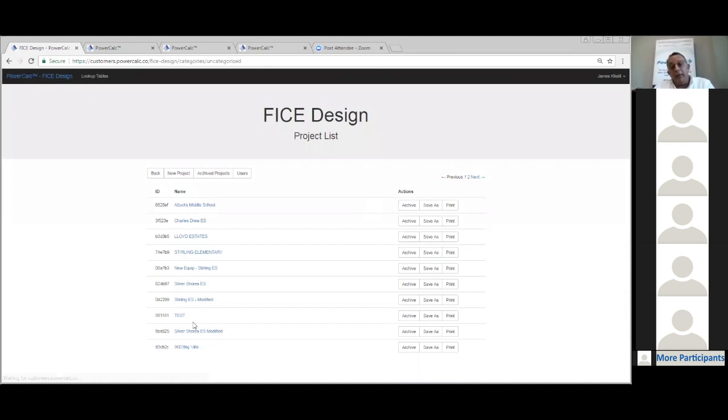So we went back to the developer and to the owner, and showed them the problem. They went back and asked the engineer of record to redesign the facility based on our recommendation, and that saved a little bit over $2 million just in the electrical distribution equipment.